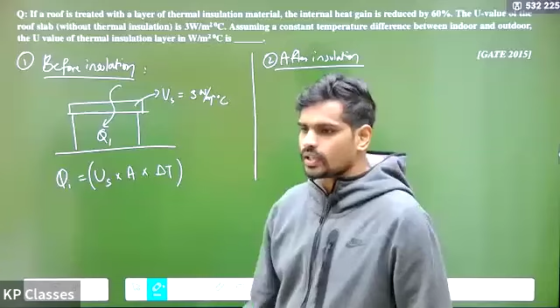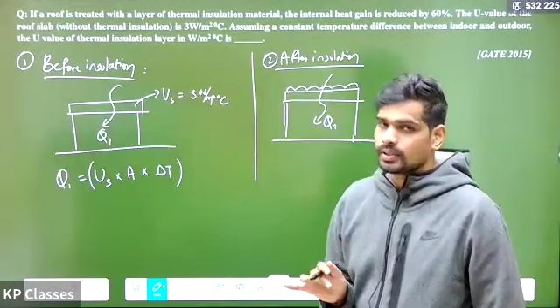In the second case, to reduce the heat gain, they applied an insulation layer on the top of the same slab. Now the heat gain in the second case, Q2, they're saying is reduced by 60%. So if something reduces by 60%, the remaining part will still be 40%. Heat gain after insulation, Q2, is given as 40% of Q1.